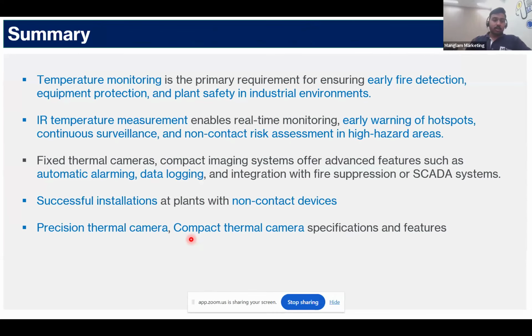To wind up, temperature monitoring is the primary requirement for ensuring fire detection and equipment protection. IR temperature measurement enables real-time monitoring with early hotspot detection, continuous surveillance, and non-contact risk assessment of high hazard areas. Fixed thermal cameras offer advanced features like automatic alarm on reaching threshold temperatures, data logging in Excel sheets or graphical representation, and integration with fire suppression or SCADA systems - our analog and digital outputs can also be integrated with SCADA systems.